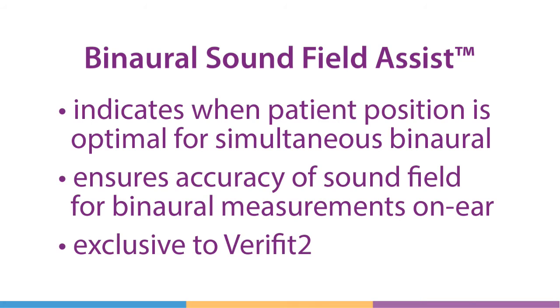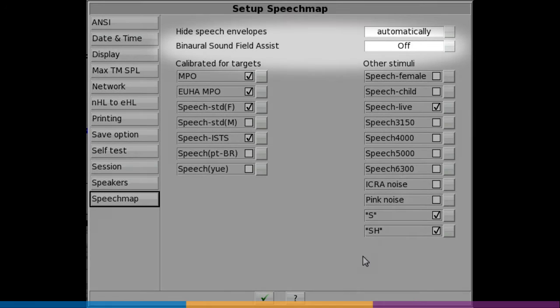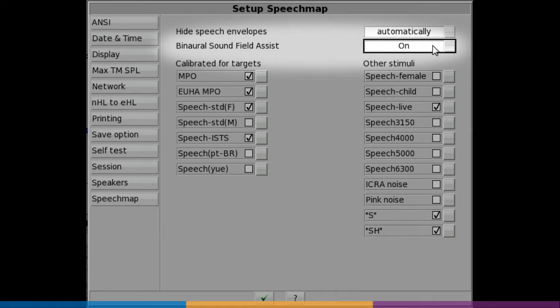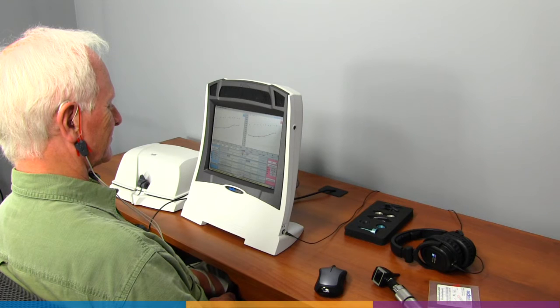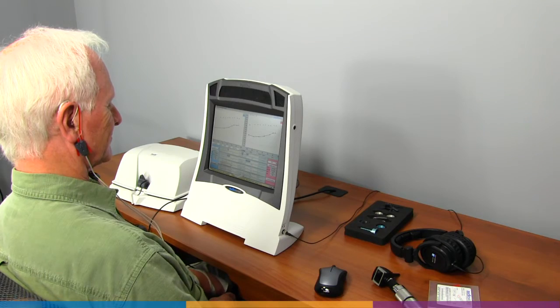If an imbalance in the input level or spectrum across ears is detected, the user is prompted to adjust the client position to correct it. First, in setup, select speech map and ensure the binaural sound field assist tool is active. Set up the patient for speech map testing as normal.